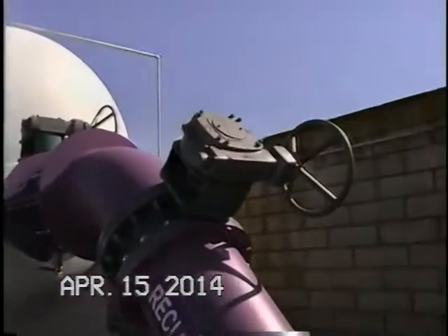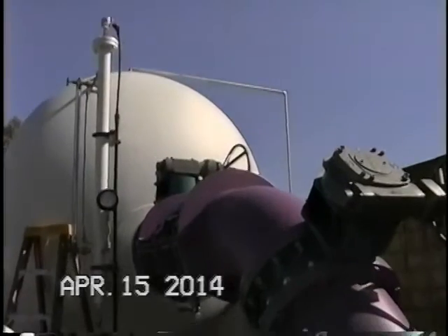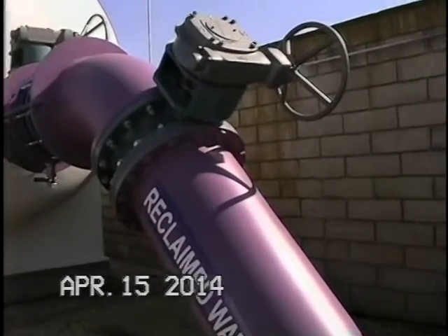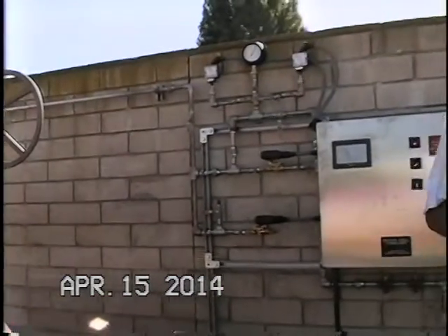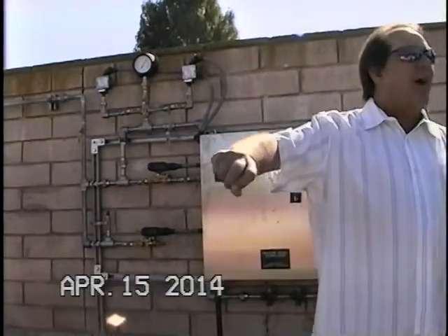We've got a tank that's been sized specifically for this project, and it will dampen the effects of the starting and stopping of the pumps. And if we had an emergency shutdown with full maximum flow, it's there to protect the pipeline from any transient surges. The easiest way to relate to it is when you go into an older house, turn on a faucet, then shut it off, and you hear those pipes rattling. That's really what we call a surge, that water hammer effect. What these surge tanks do is dampen that effect.